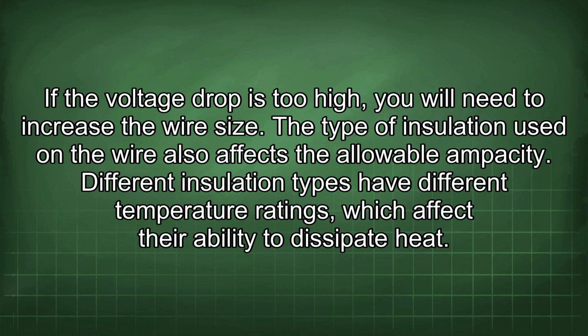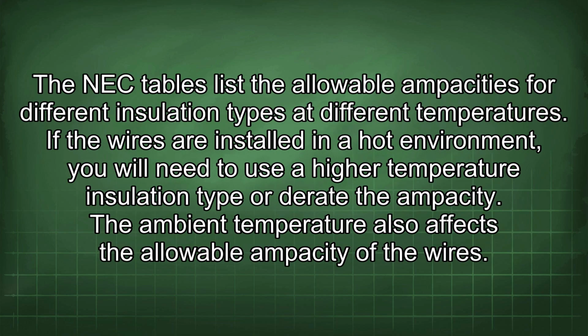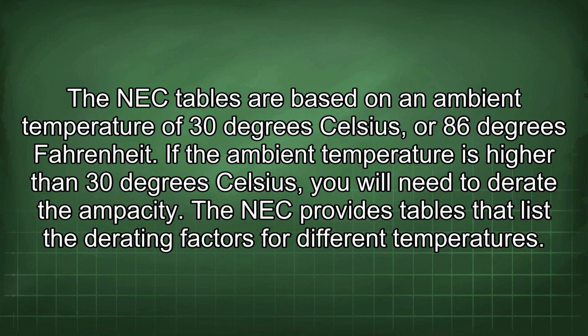The type of insulation used in the wire also affects the allowable ampacity. Different insulation types have different temperature ratings, which affect their ability to dissipate heat. The NEC tables list the allowable ampacities for different insulation types at different temperatures. If the wires are installed in a hot environment, you will need to use a higher temperature insulation type or derate the ampacity. The ambient temperature also affects the allowable ampacity of the wires. The NEC tables are based on an ambient temperature of 30 degrees Celsius or 86 degrees Fahrenheit. If the ambient temperature is higher than 30 degrees Celsius, you will need to derate the ampacity. The NEC provides tables that list the derating factors for different temperatures.